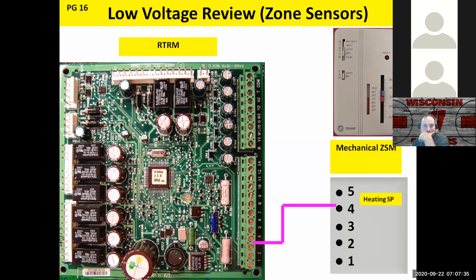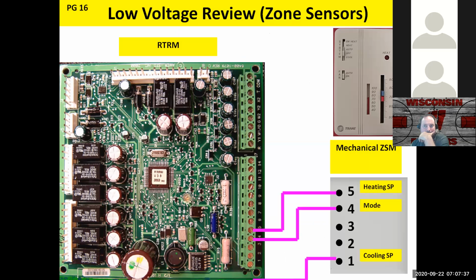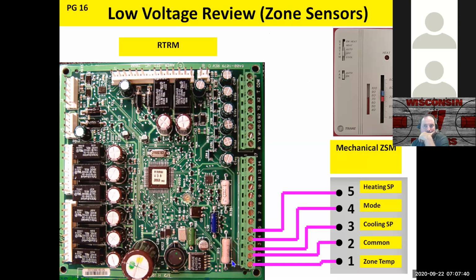Now, on the board, there are terminals 1 through 14, and then there's R, W, G, Y, and there's a hierarchy of controls on how this works. So, number one is if you have a LonTalk card or a TCI 3 card or a TCI 4 card connected, that's priority 1. So when you have a communication card connected, these terminals don't work. They're deactivated at that point.